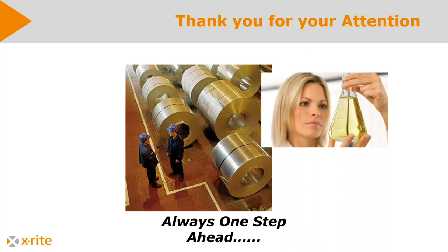Okay. Is there an influence of ambient light? Basically the same answer. This is the flash lamp technology. So the flash is much more intense than any ambient light which goes on. If the sun is shining on the product, if you use a flash lamp lighting into the instrument, lighting onto the measurement spot, there is definitely no influence. One trick is also that we make a measurement right before we do the flash. So we measure the ambient light, and then we measure, of course, the flash, and the flash is the energy from the flash plus the ambient light, and we subtract the ambient light, and so we have only the flash. This is a technology which is widely used for any inline instruments to get rid of the ambient light, so it has no influence at all.